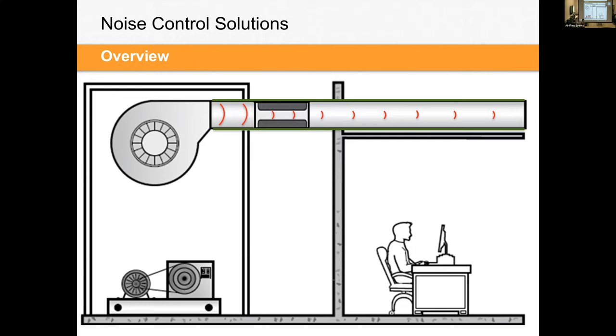When we schedule it then, do we factor, I mean, we probably should state system effect. I guess we put a schedule on their pressure drop, but should you put ideal condition and system, put both on there so you know you're getting apples to apples? Ideally, yeah, if you had both. The thing that we see quite a bit is, you'll have 10 silencers scheduled with system effect pressure drop: 0.17, 0.12, 0.13. But then you're like, well, what are the system effects assumed? You need to know what they are. Is it an elbow? Is it a broad plenum? Is it a fan? If you don't have the mechanical drawings or the plan layouts and you just have the schedule, you're missing one of the pieces of information. So it gets a little bit complicated like that.